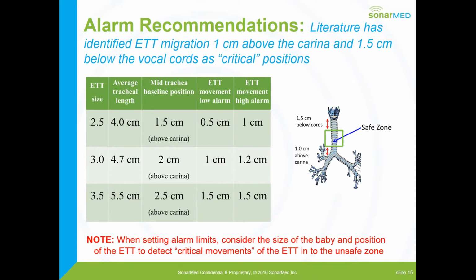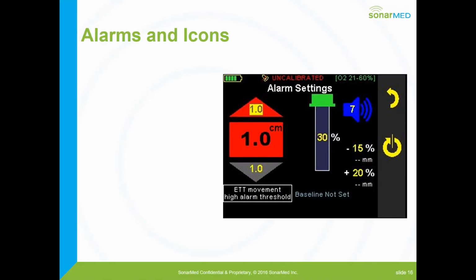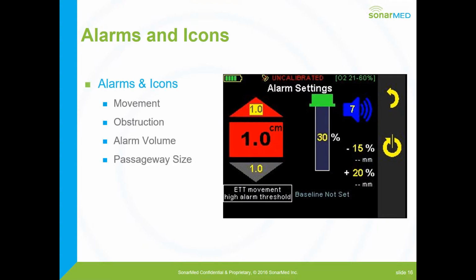So again, you consider the size of the baby and the position of the endotracheal tube, and you want to detect critical movements, anything that goes out of our safe zone and into an unsafe zone. So this is your alarm screen. We showed you a minute ago how to get in there. What you see highlighted right now is a 1.0 and a red arrow up. What that means is that I'm going to alarm at this point if my endotracheal tube moves up more than 1 centimeter. I have alarms for movement, obstruction, and passageway size. I can also set my volume here.